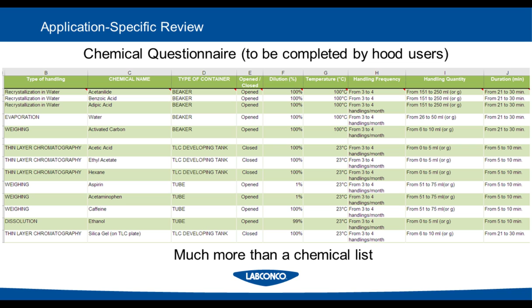And in that report and that approval, we'll go through everything provided by the hood users, and we'll, from a safety perspective, at the very top of this slide, we'll look at containment. Is everything you declared to be used in this hood going to be contained by the hood? Now, this doesn't matter if it's ducted or ductless. In this case, we're just looking at what is it you're using. And an important part of this also is just making sure that everybody knows, to be crystal clear, this is a chemical fume hood. This is not a biosafety cabinet. Sometimes we say filtered, people start to think of BSC, a biosafety cabinet, which is also HEPA filtered for biologicals. Biologicals are not approved for use in these hoods.